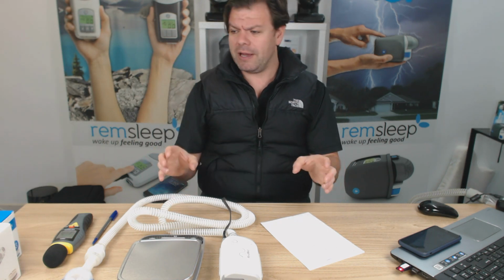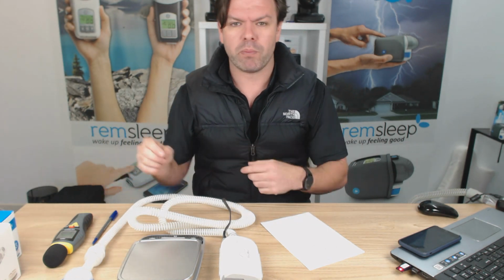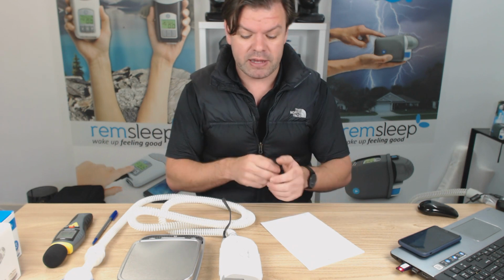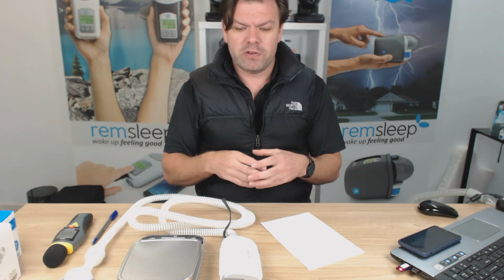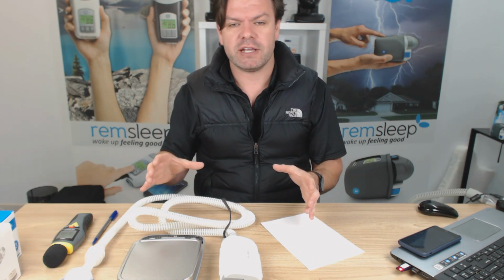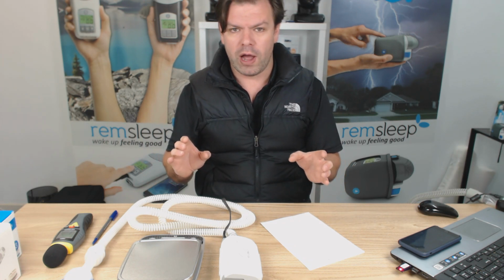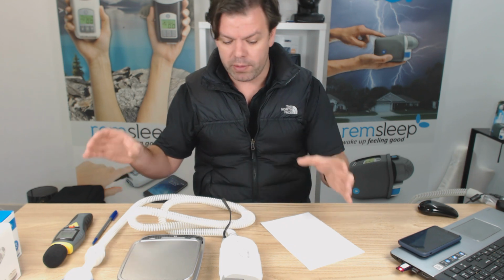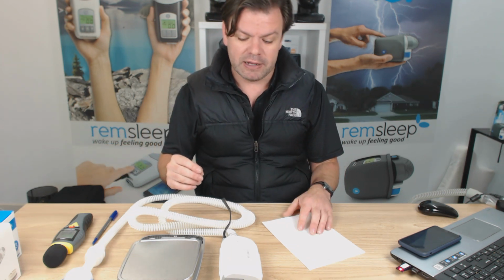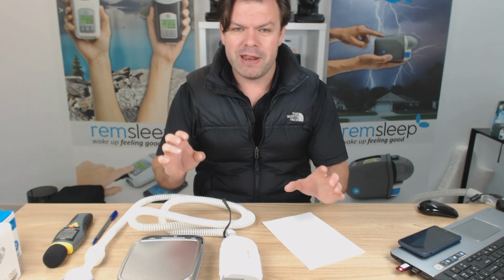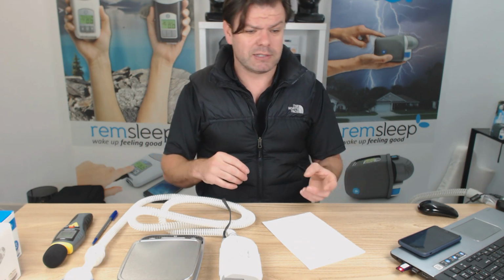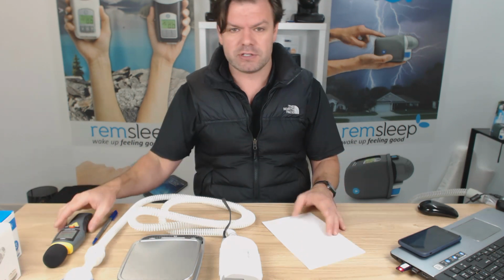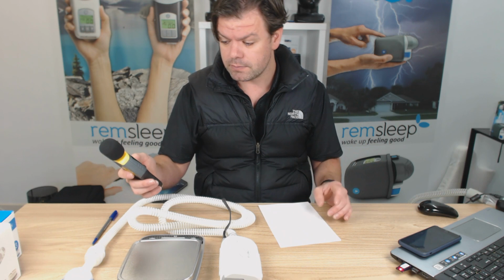They do it in this really strange environment where they don't actually have someone breathing on the tube. They basically plug the end up, turn it on. When you don't have anyone breathing on the machines, you get a completely different noise level than when you actually have someone breathing on the device.